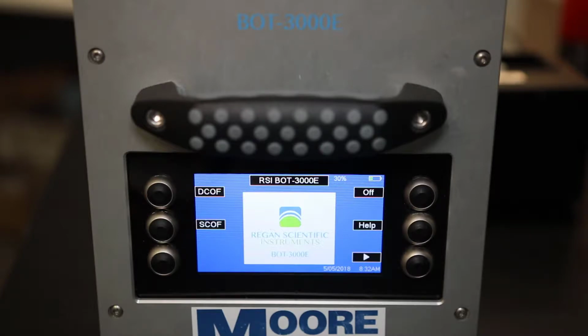This is essentially the yearly calibration of the device, which is completed by the manufacturer and is critical for its continued reliable and accurate operation. It is important to remember that before you conduct any testing, you must verify that the device has been calibrated within the past 365 days from the date of its use. The last calibration date will be included on the PDF reports created by the BOT.